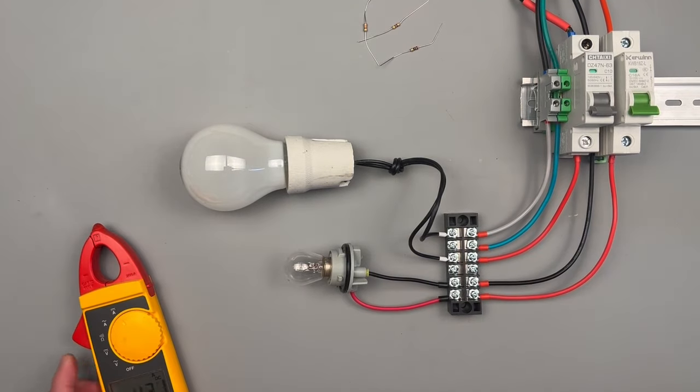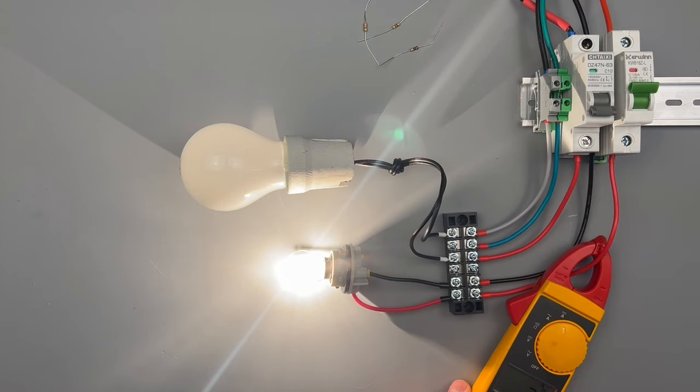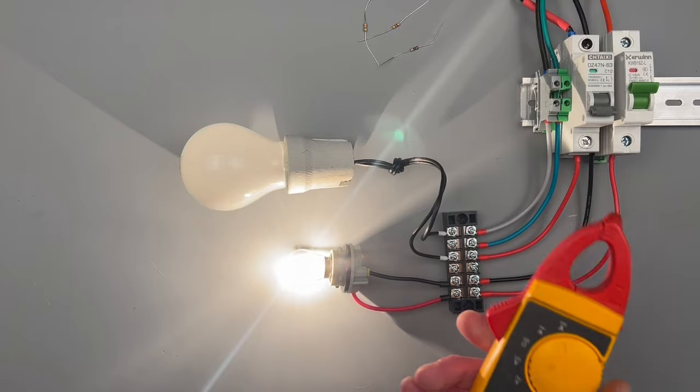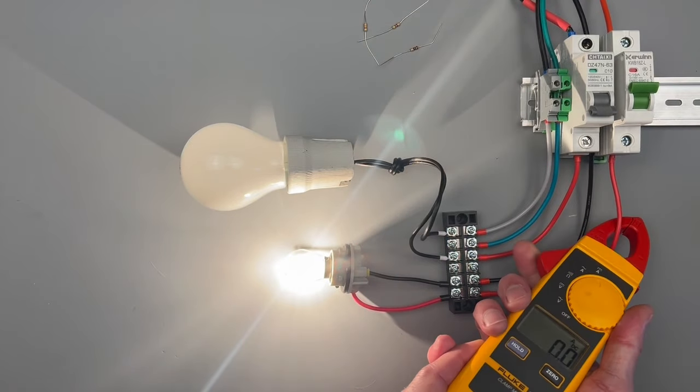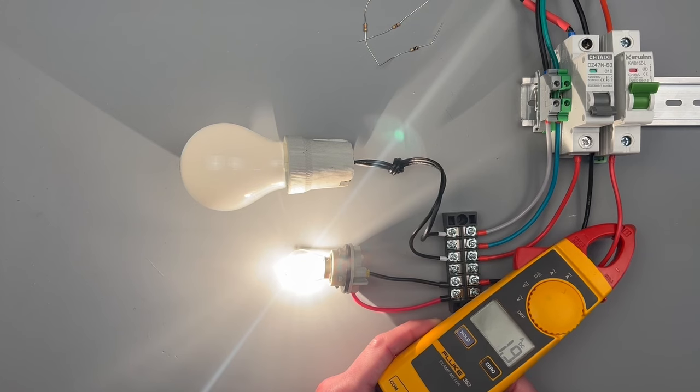It's showing about two and a half amps here on the meter but I know that's not 100% accurate. You need to make sure we zero out our amp clamp before we take a reading. Okay, now it's at two amps. I know that that's accurate.